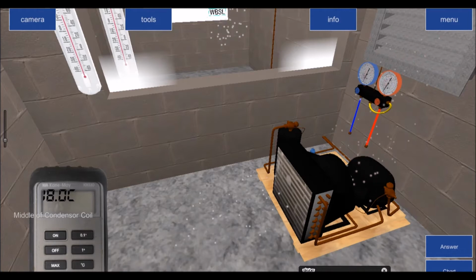Crankcases of compressors are usually low pressure, low temperature. In other words, they're on the low side of the system, and that would continue to allow discharge gas into the low side of the system, which would give you the reading of a lack of compressor capacity. In other words, head pressure decreases, back pressure increases, temperature goes up in the room, a sign of lack of compressor capacity. So you might find it's a result of an accessory. So again, depending on the system, that requires further investigation.